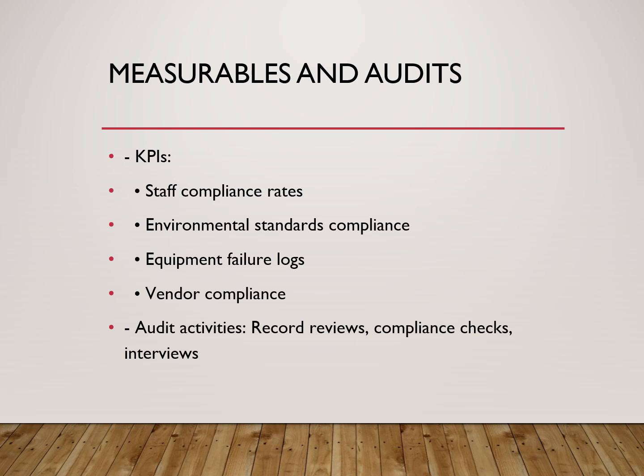The second one is the KPIs are just for show trap. A lab in Nairobi tracked equipment uptime as okay, not okay, with zero hard data. The analyzer had been failing 30% of runs for months. How do you survive this? Quantify everything. For example, freezer temperature excursions: 0 out of 30 days. Do trend analysis. Why did reagent waste spike in December? Did you have reviews? Did you have recalls? Did you have rechecks?